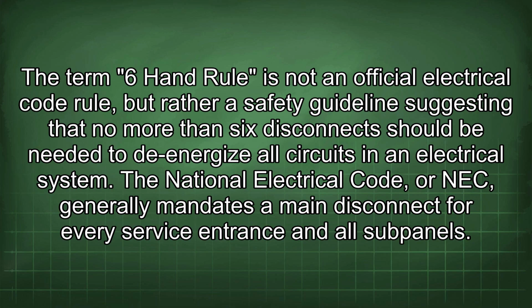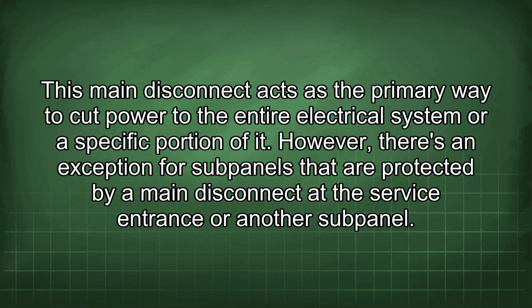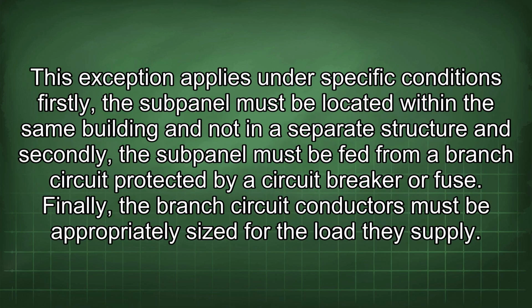The National Electrical Code, or NEC, generally mandates a main disconnect for every service entrance and all subpanels. This main disconnect acts as the primary way to cut power to the entire electrical system or a specific portion of it. However, there's an exception for subpanels that are protected by a main disconnect at the service entrance or another subpanel. This exception applies under specific conditions.